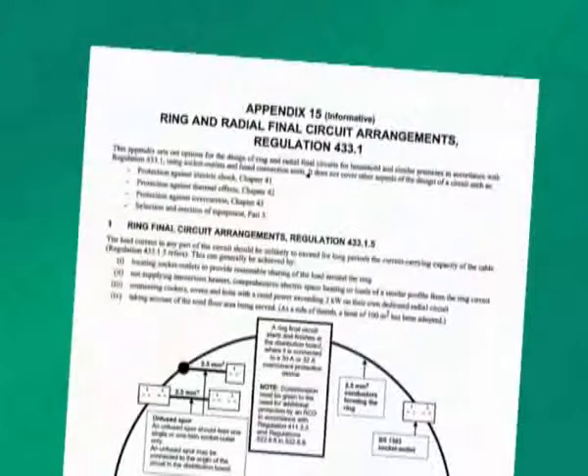Because the resistance is a parallel one, it's very difficult to determine whether a bridge or interconnection exists by measurement alone. But if you can estimate the length of the circuit, you can calculate the expected resistance. And if you consistently get much lower readings than this, then it's reasonable to expect there may be a bridge or interconnection.